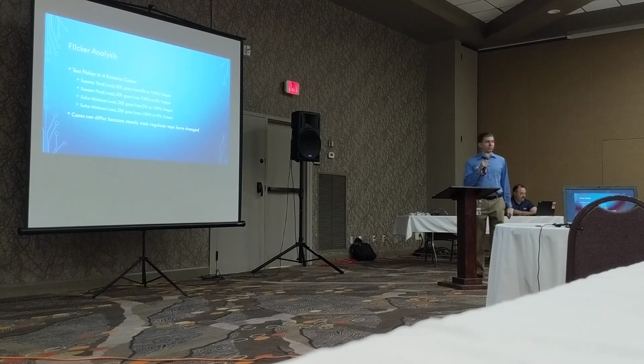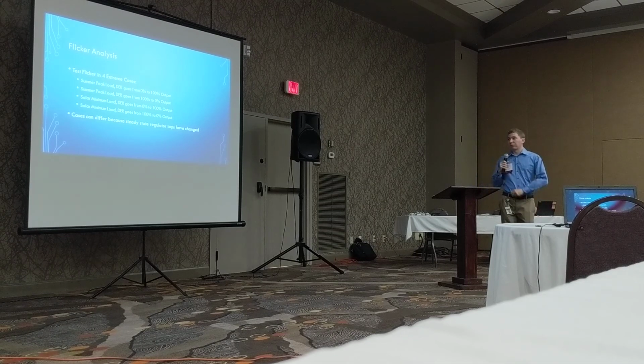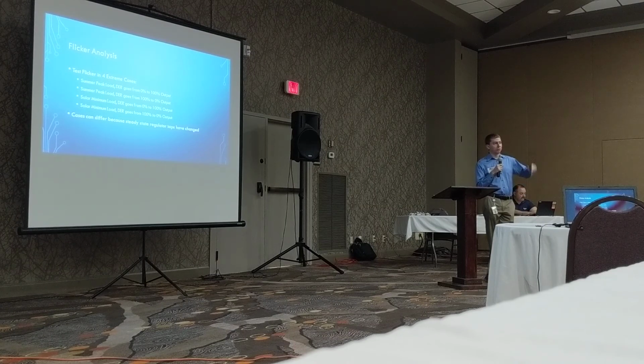So I've said flicker a couple of different times. Our flicker process we run in 4 different cases. We run at the peak load and at the minimum load, and we go from 100% output to 0%. That's a little bit extreme, but we'll make a couple of different conservative assumptions in here just to make sure that we're not going to have these flicker types of issues, because these are very difficult to actually fix once you put it on the system without spending in the 7 digits.